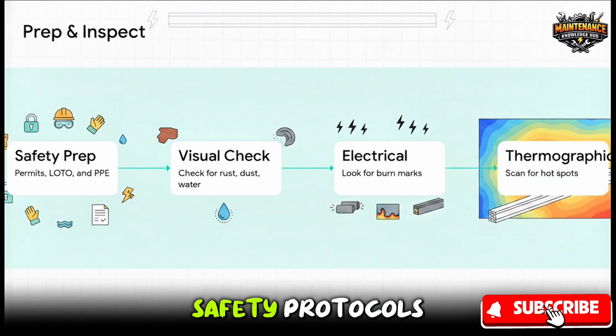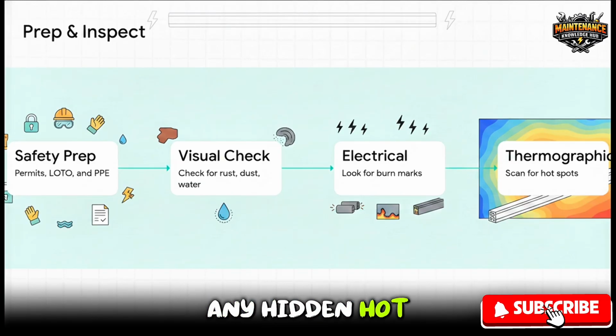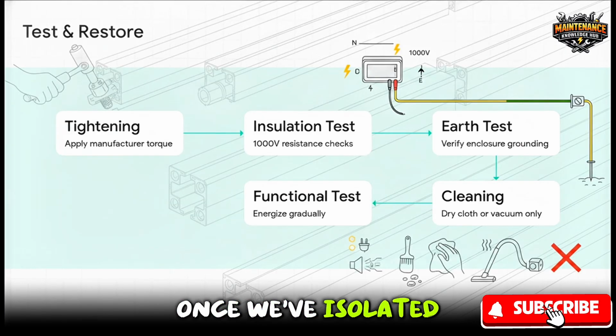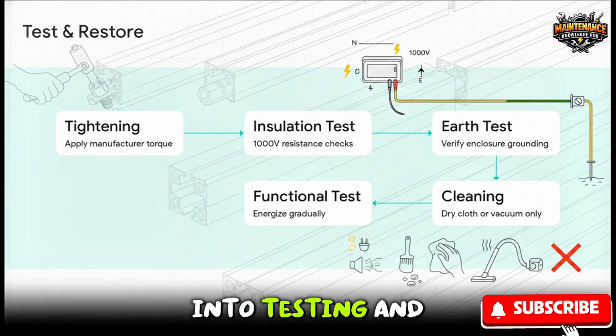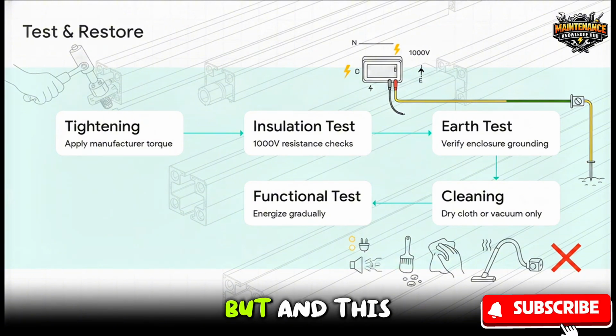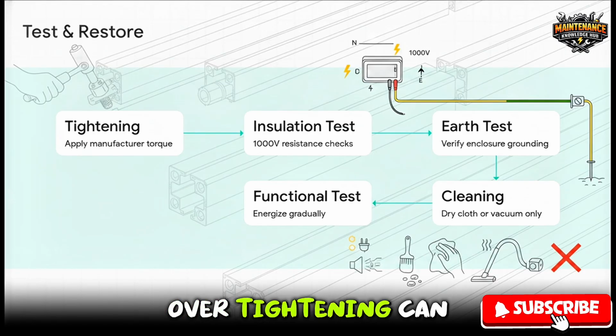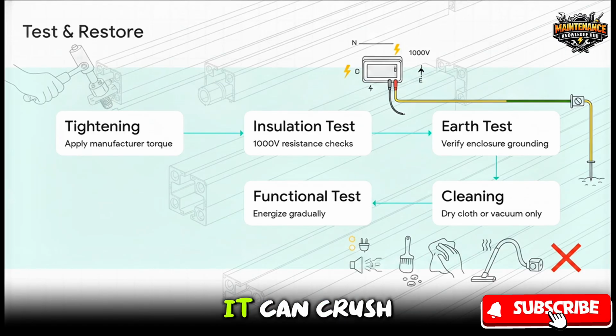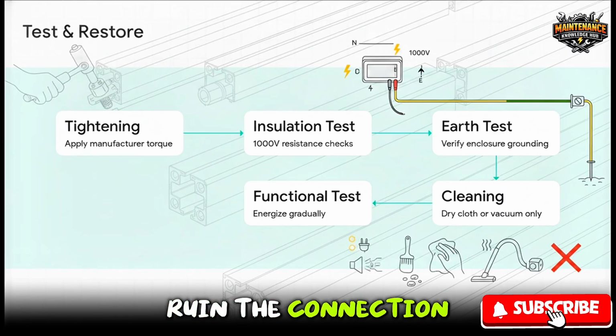Following those strict safety protocols, you use a thermal camera while the system is energized under its normal load to scan for any hidden hotspots. Once we've isolated the system again, we move right into testing and restoration. Step 1 here is tightening. But, and this is a big but, you must apply the exact manufacturer torque values. Actually, over-tightening can be just as bad as a loose joint. It can crush the insulation and ruin the connection.